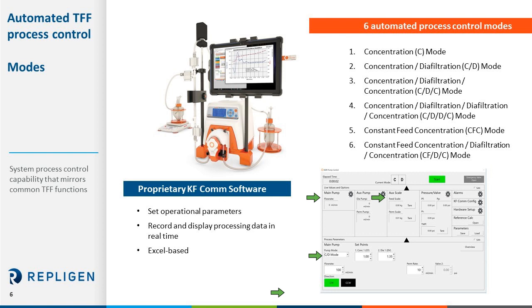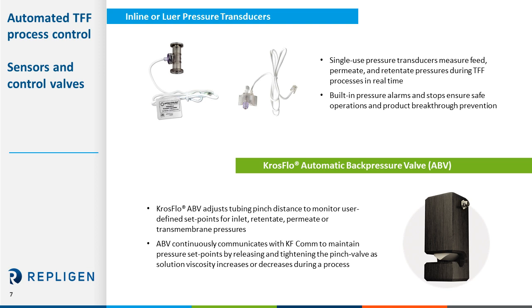For those who perform TFF, it is important to understand the pressure profiles of your process. Knowing the pressures within your system is a good way of tracking membrane performance and is also a key parameter for scaling up in the future. Inline or luer-connected single-use pressure transducers are key components of the KR2i and allow for real-time process monitoring of feed, permeate, and retentate pressures. Pressure alarms and stops are built-in to ensure safe operations and product breakthrough prevention. For example, a drastic drop in feed pressure may suggest a leak, and the system can warn users and stop the process immediately.